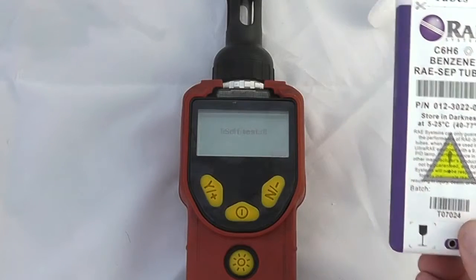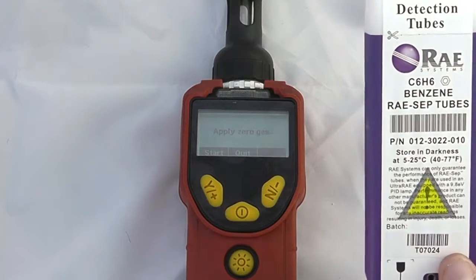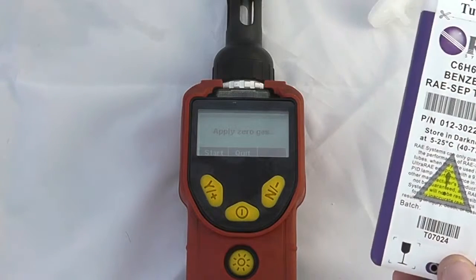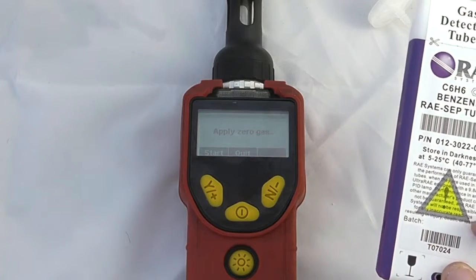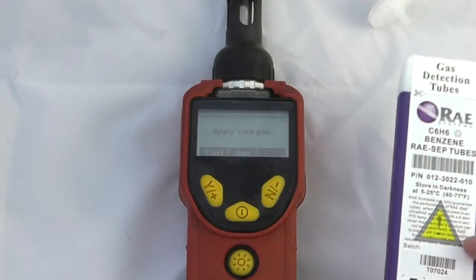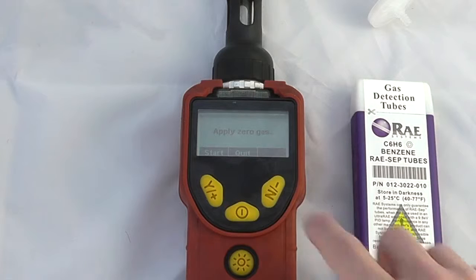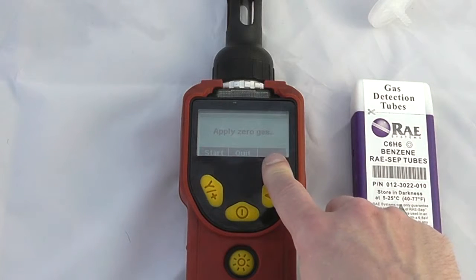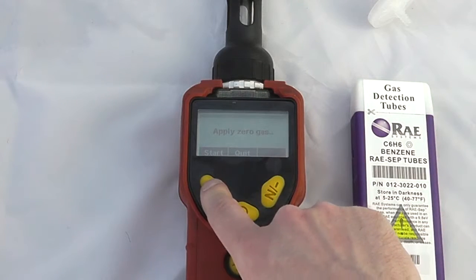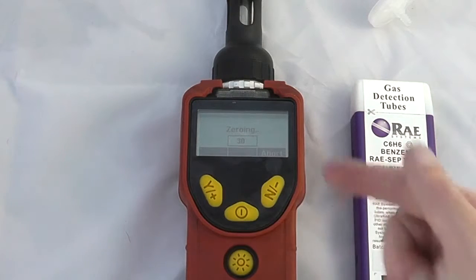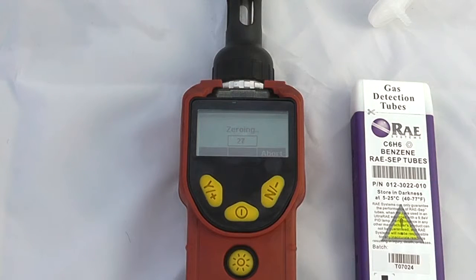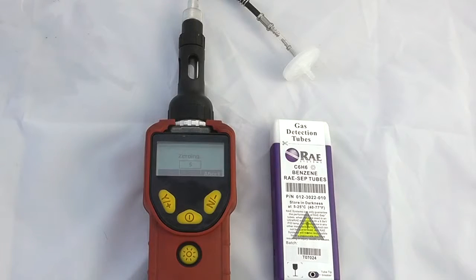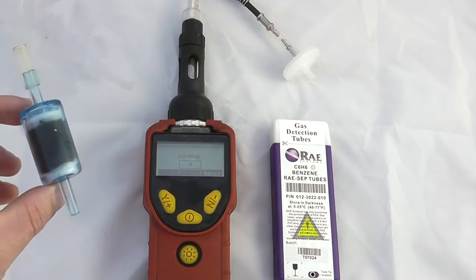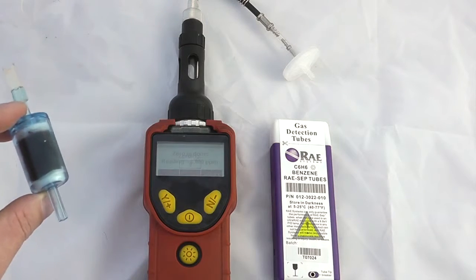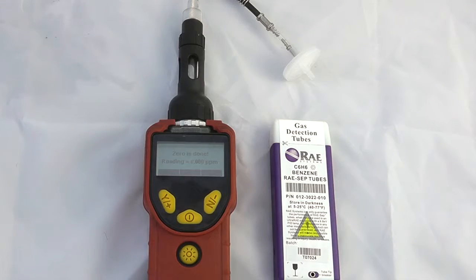The instruments are supplied with a pack of gas detection tubes. These are separation tubes, so the logic being that they will only let through benzene only. To begin with, the instrument has a zero on startup enabled, so I'm going to do a startup zero on the instrument. This is a 30-second basic fresh air calibration of the instrument. There's a carbon filter supplied by RAE Systems that we can use on the top of the instrument if there's any potential for VOCs in the atmosphere.